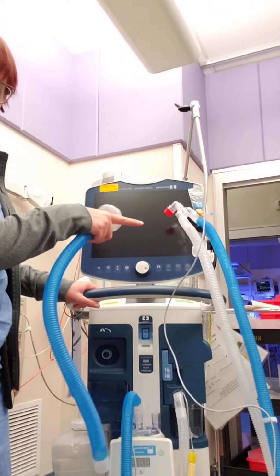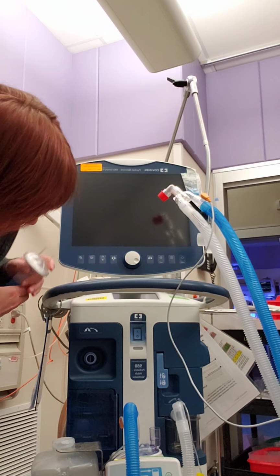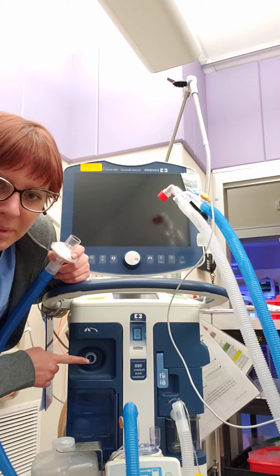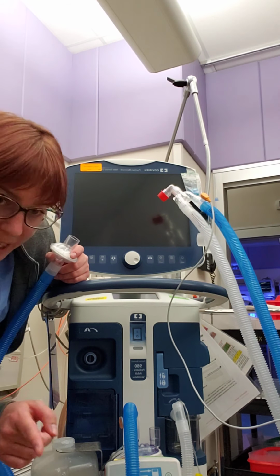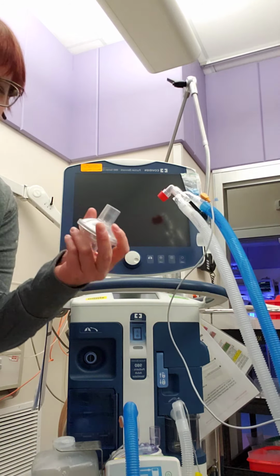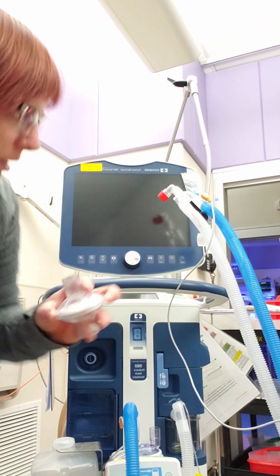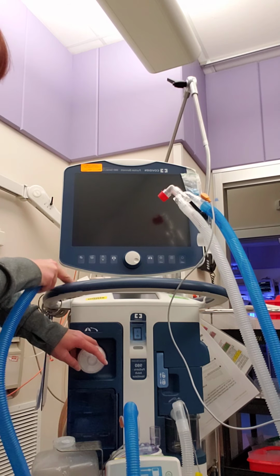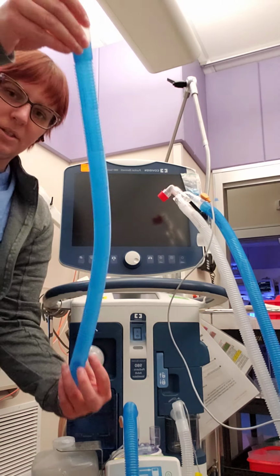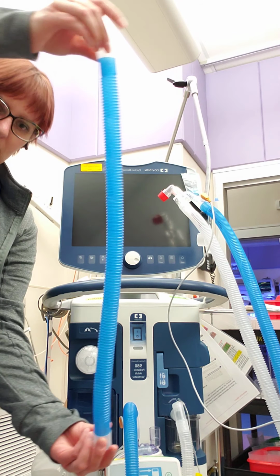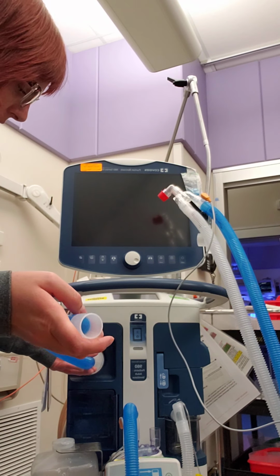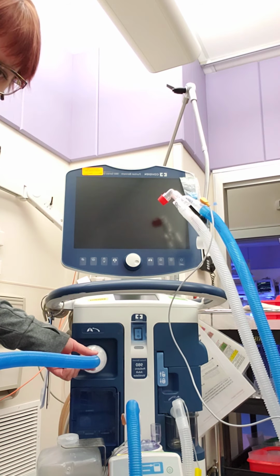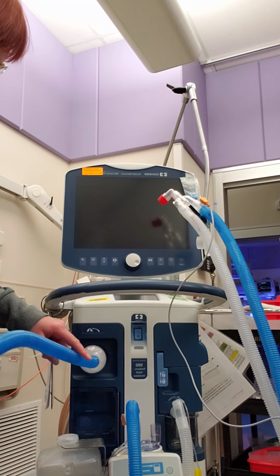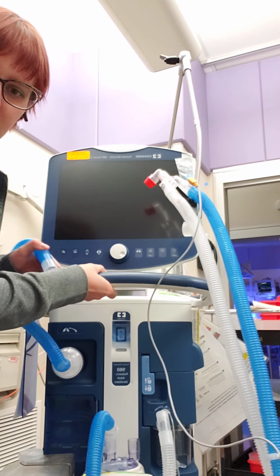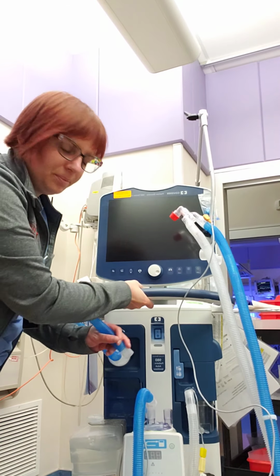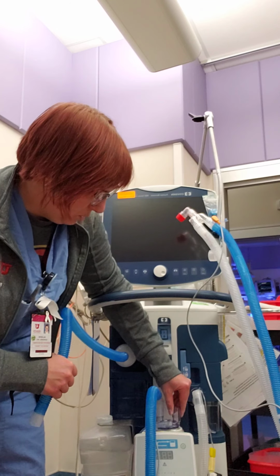So just as with the 840 or any other ventilator, we have a connection from the ventilator out to the patient, except this time we still place our viral filter, just as with the non-heated. Stick it right there. And then we have this short piece of corrugated tubing. This short piece connects to the inspiratory from the ventilator. And then what's different, there we go, is we hook it to the heater.